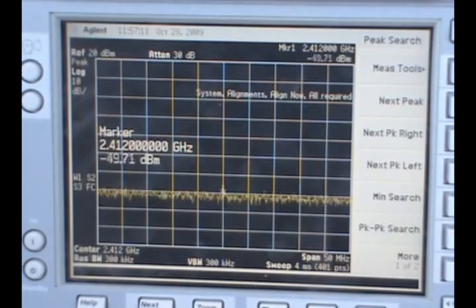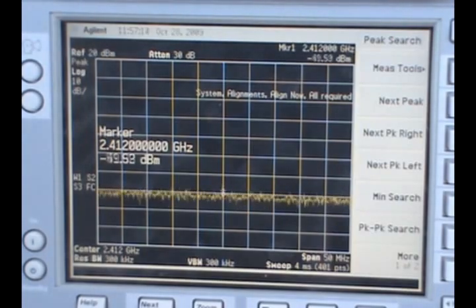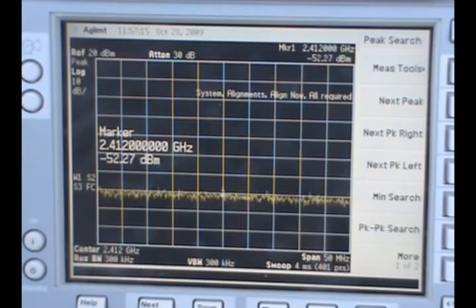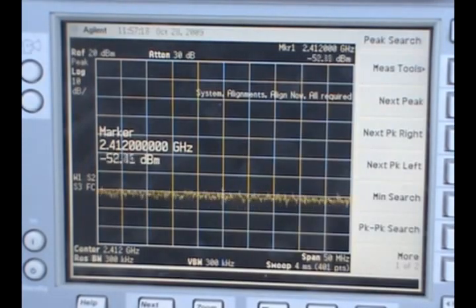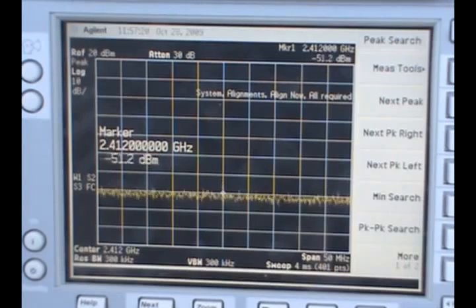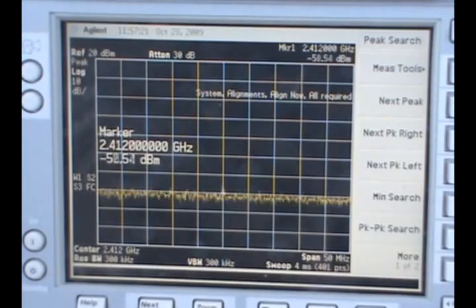Getting back to the LabTool again. We use command 22 with parameters 1 and 15 to set channel to 1 and power to 15 dBm. I will use that command now.